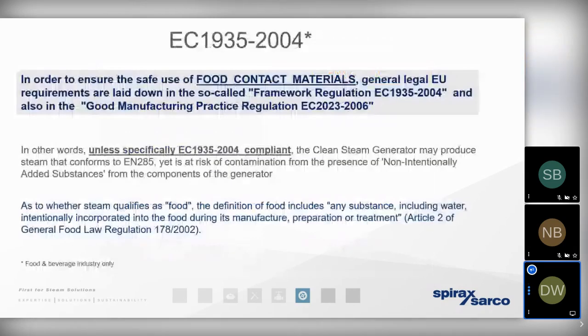But in the food and beverage sector, there's a further consideration, and that's a standard that we know as EC 1935-2004. And that basically states that any product that comes into contact with foodstuffs has got to be EC 1935-2004 compliant. And of course, steam will come into contact with foodstuffs if and when it's used for direct injection or indeed sterilization. So that means that the steam generator itself must also be EC 1935 compliant.